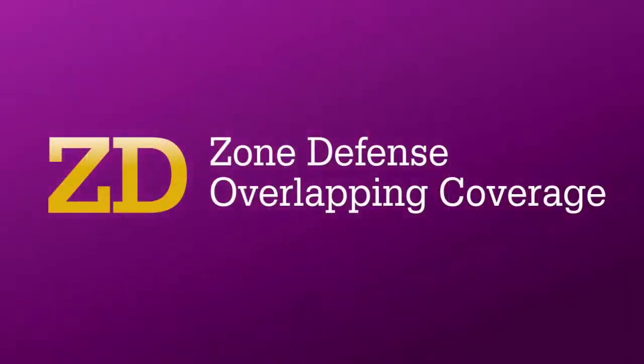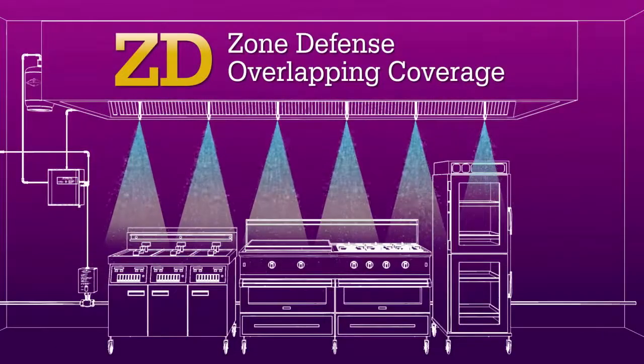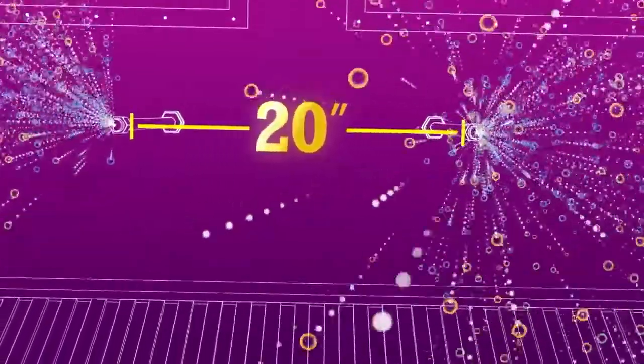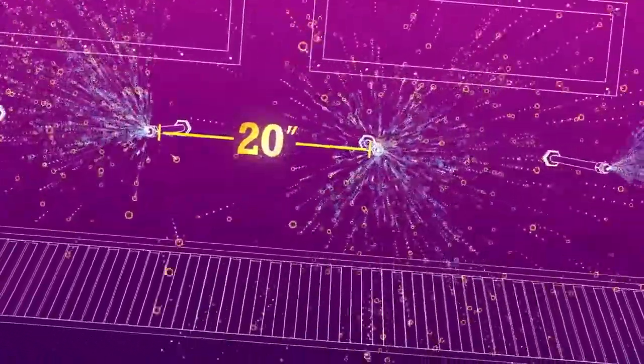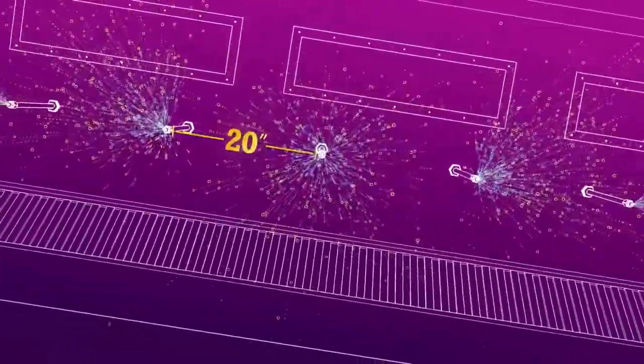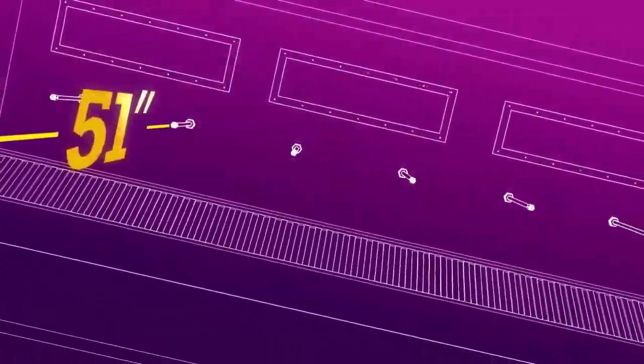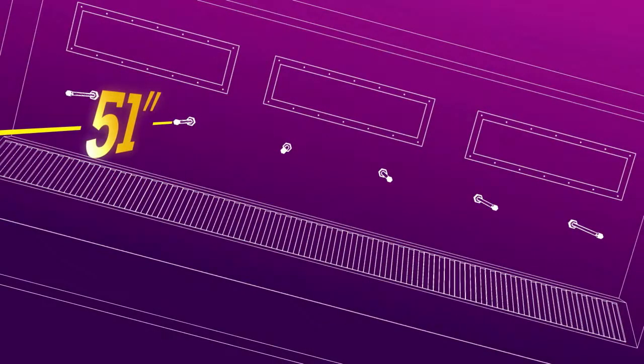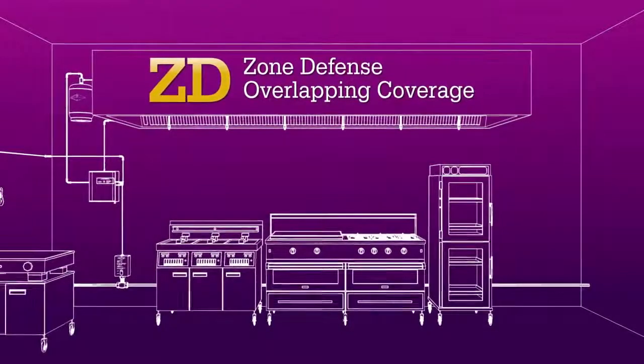While our ZD or zone defense system offers overlapping coverage in which identical nozzles are spaced 20 inches apart regardless of the appliance, this creates an overlapping discharge pattern. With the ZD system, nozzles can be placed up to 51 inches above the appliance and centered in the zone of protection. Amerex was the first to offer overlapping coverage.